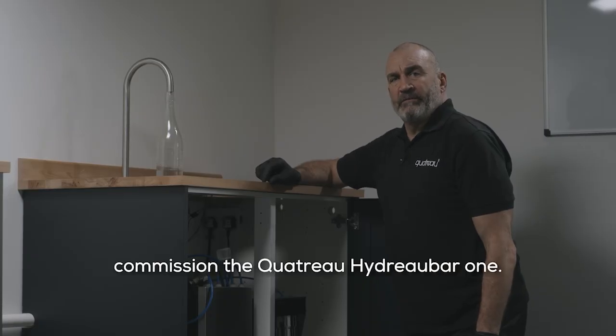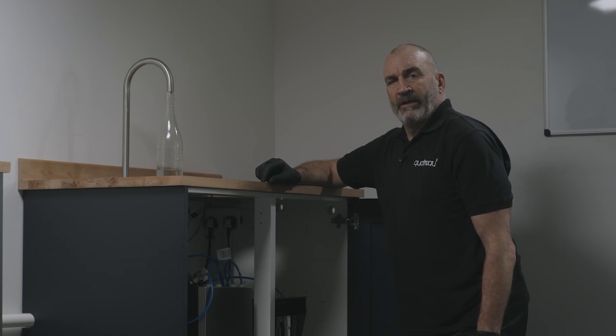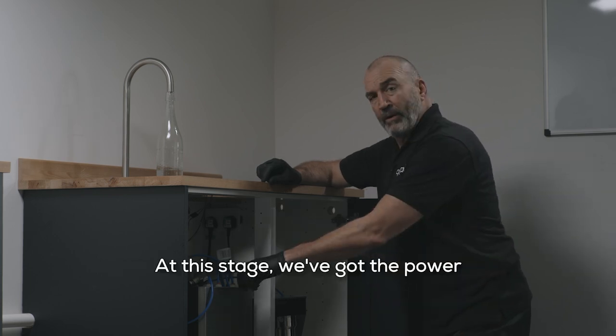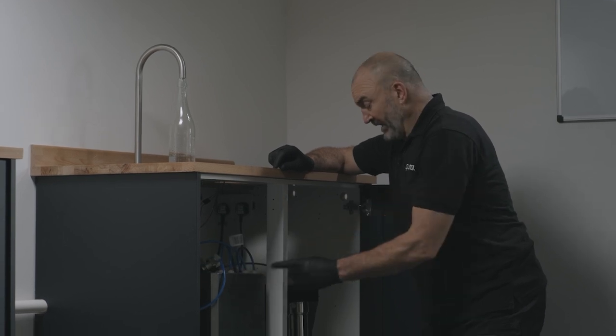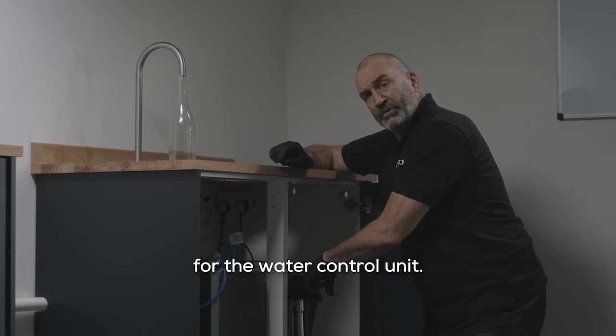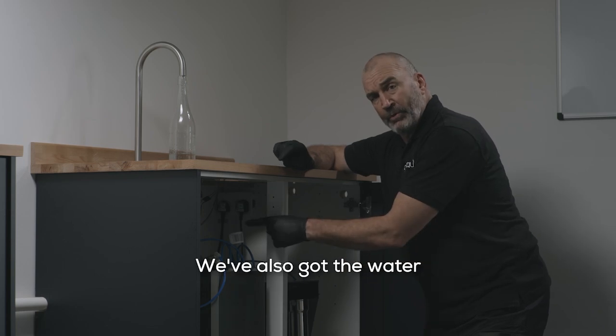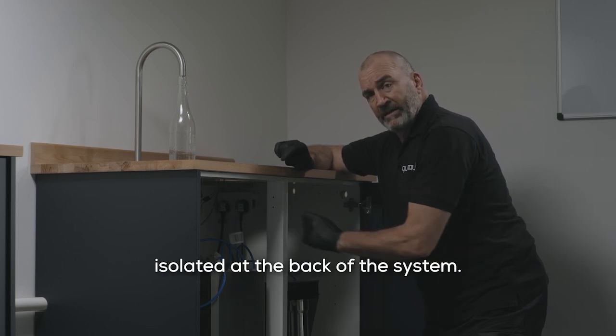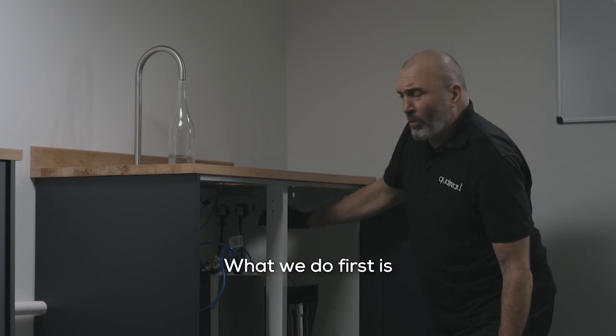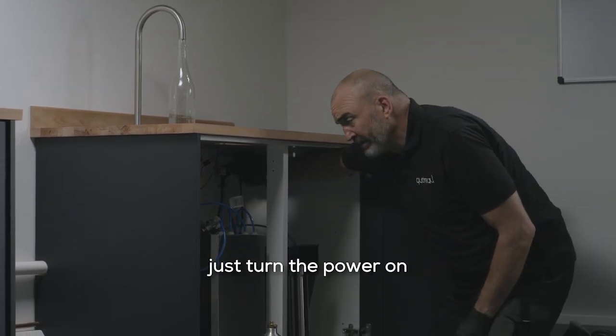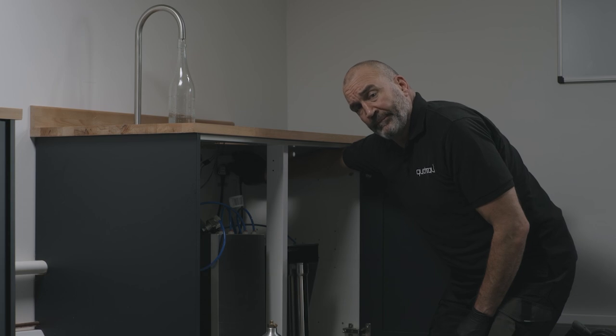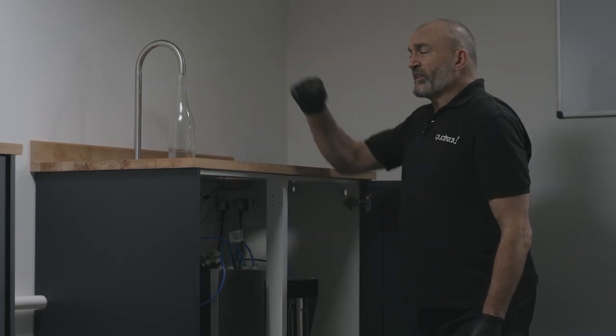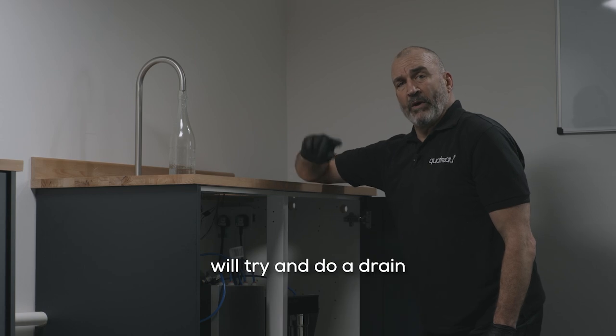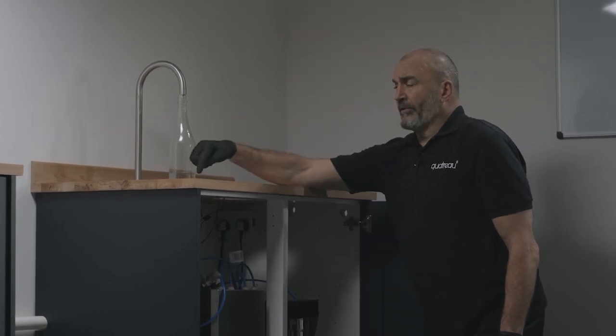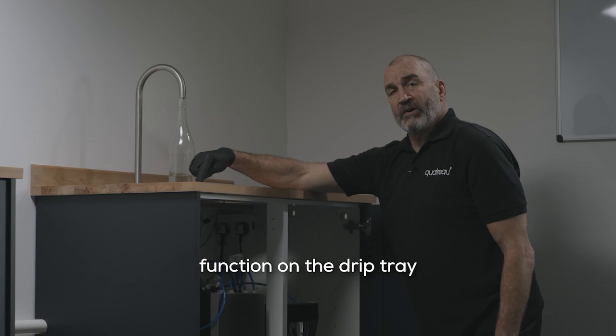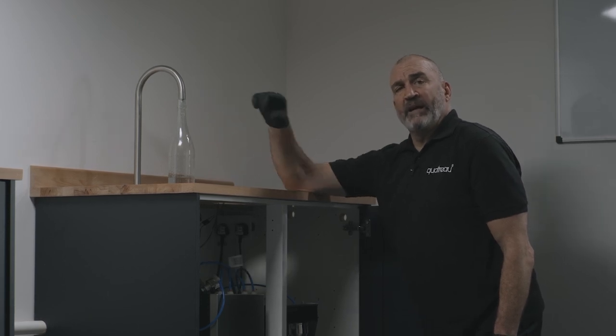We're now going to commission the Quatreau HydreauBar 1. At this stage, we've got the power switched off for the chiller and the power switched off for the water control unit. We've also got the water isolated at the back of the system. What we'll do first, just turn the power on to the water control unit. We'll make that noise. That's just the pump running because it will try and do a drain through the tank, just press the drain function on the drip tray and the pump will stop working.